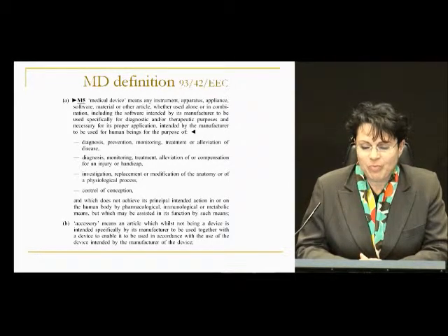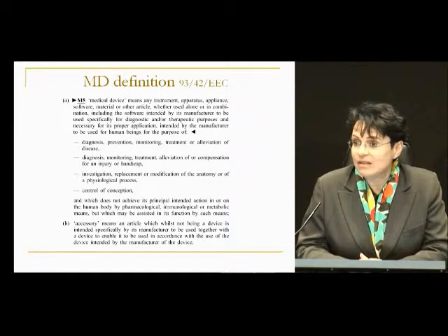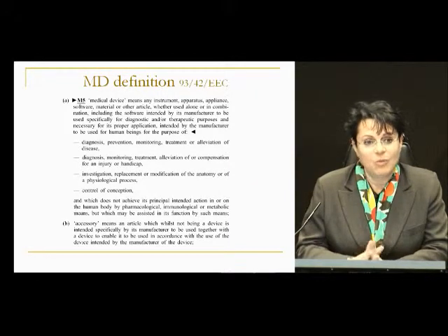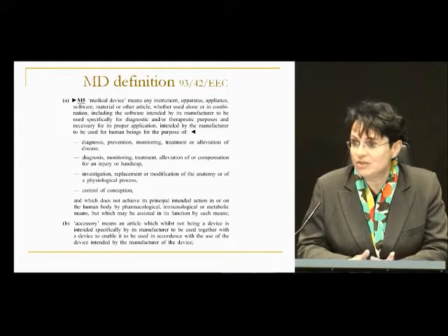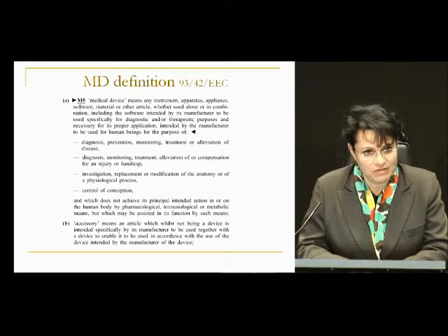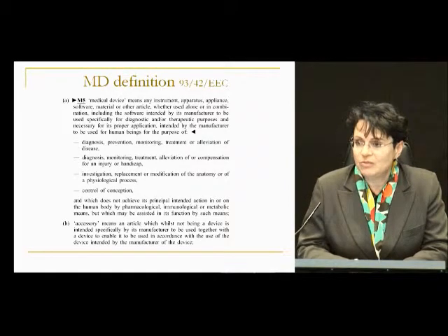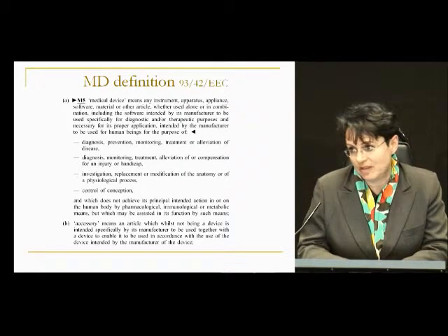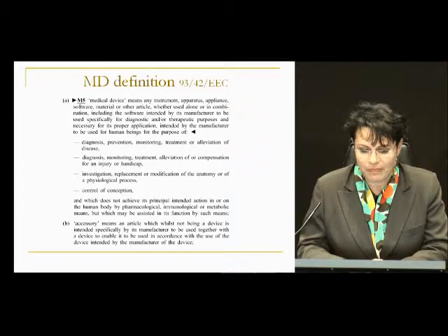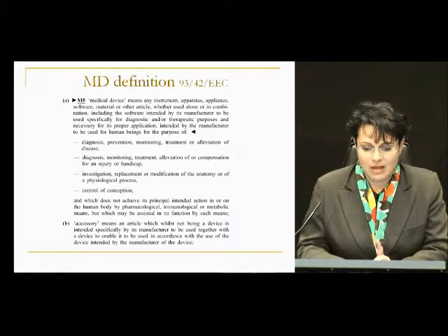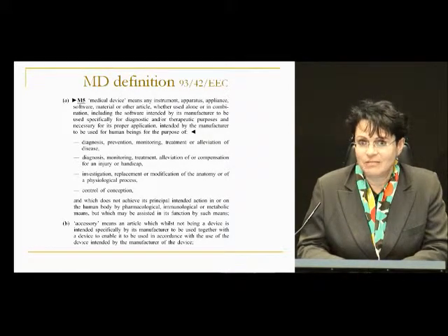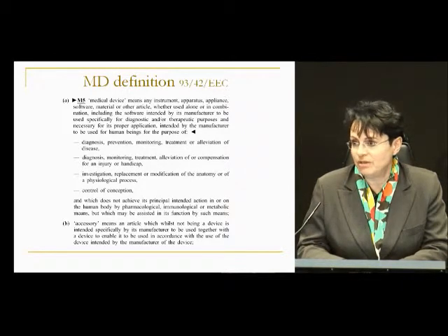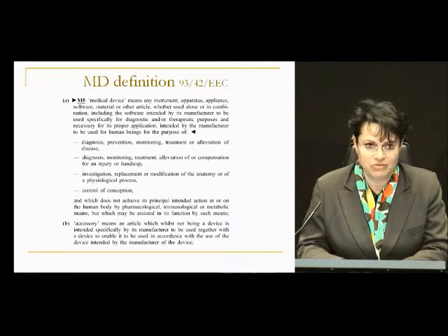The intended purpose. It is the way the manufacturer decides to place a device on the market within a very specific clinical use and not another one. This clinical use will be the starting point for finding the classification of the device as part of the directive. Proper application means that the use of the device is user-related, totally different from the drugs.